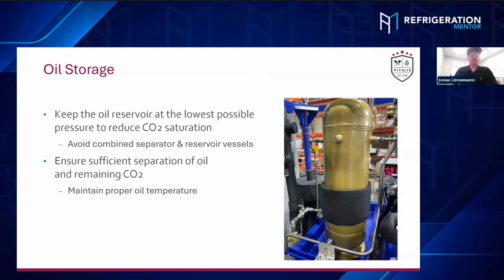So this is the oil storage vessel. As I've said before, you want to have that under the lowest possible pressure to have as much CO2 gas as possible coming out of the oil. That's why in typical CO2 systems, these vessels are connected to the liquid receiver, to be slightly above the medium temp crankcase pressure, but as low as possible.